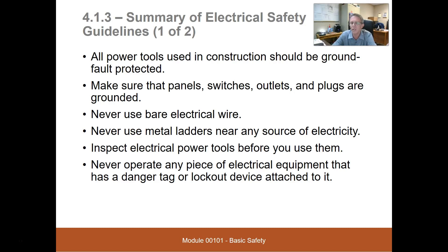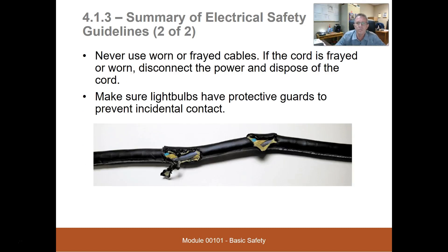Make sure that panel switches, outlets, and plugs are grounded. Don't use bare wire or metal ladders. Inspect electrical power tools before you use them. Anything you doubt is in good working order — bring it to the competent person to make a decision. Never operate any piece of electrical equipment that has a danger lockout tag attached to it. If I were inspecting this cord on this tool, I would have to tag it and take it out of service because it has burnt, exposed wires almost to the inner insulation.